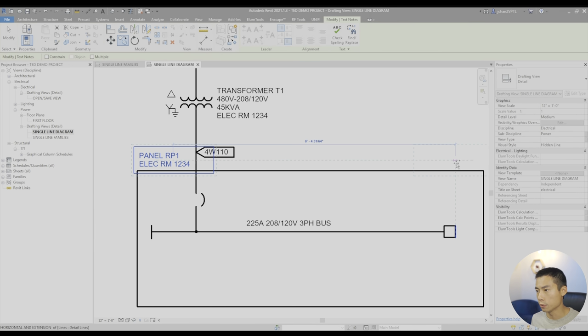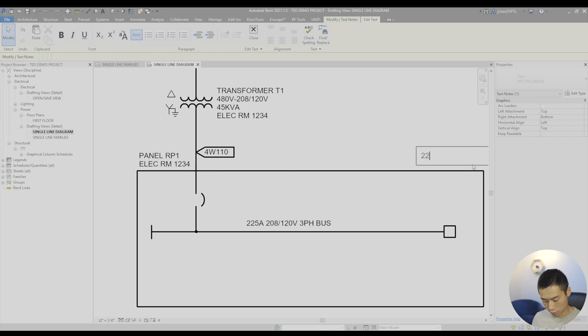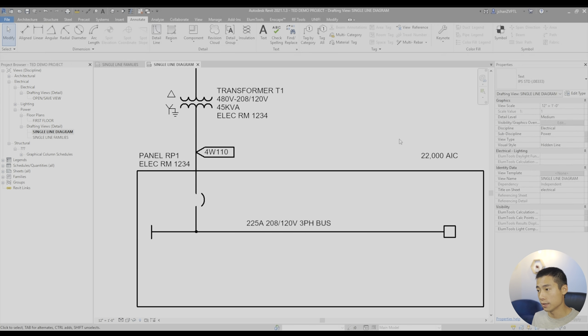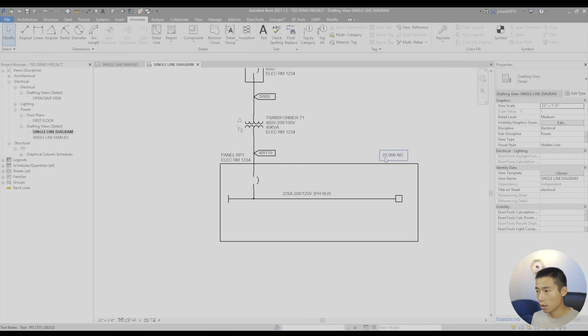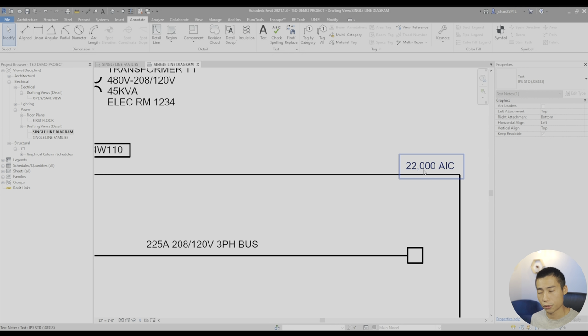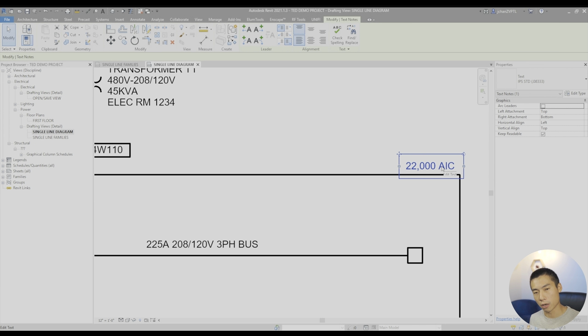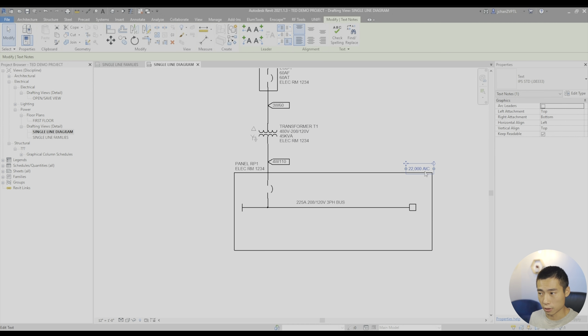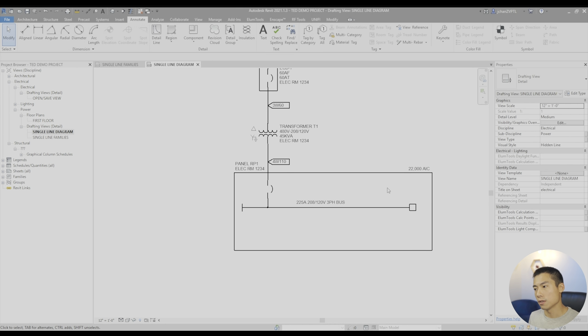Then personally, I always put my AIC rating over here. So 22,000 AIC. If you don't know what that is, it's your rating of available inrush current. Technically it's short circuit current rating, so that's what the panel's rated to. But at this point in the line, you can expect 22,000 AIC. If it's a large transformer, you can actually get really high, like 65,000 or even 150,000. So you have to make sure that your available inrush current or your short circuit current rating is listed here.